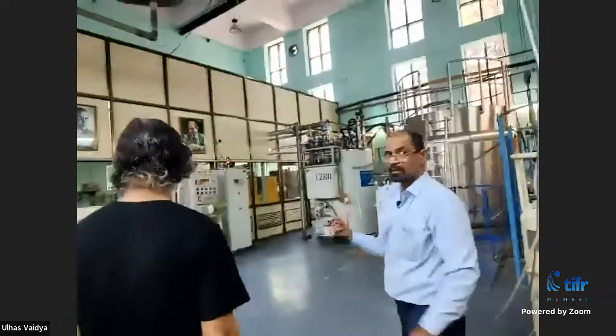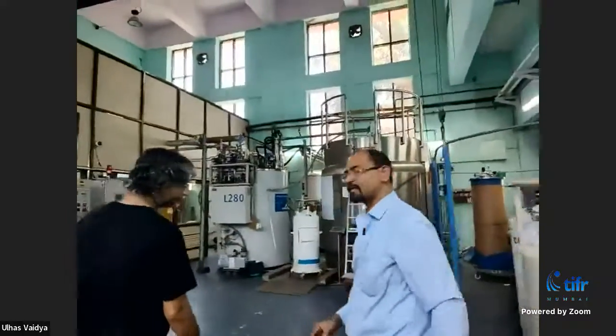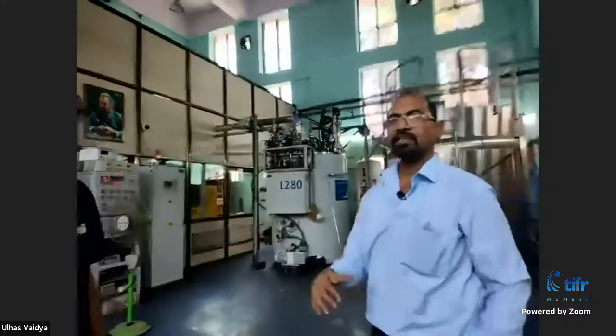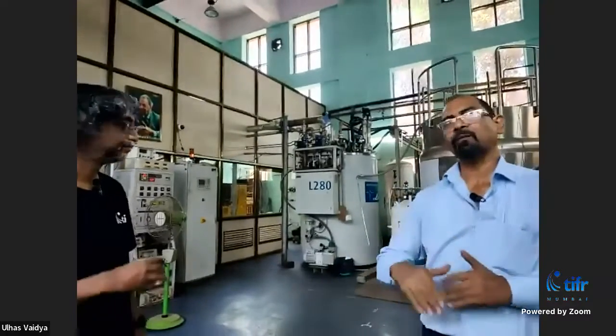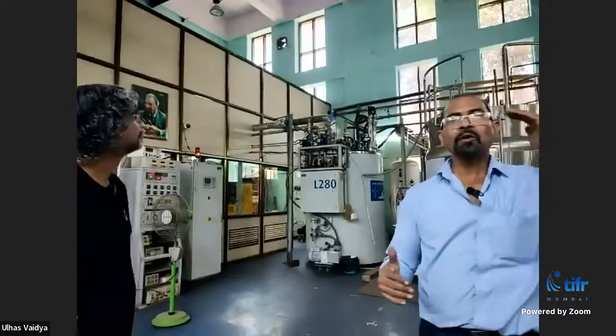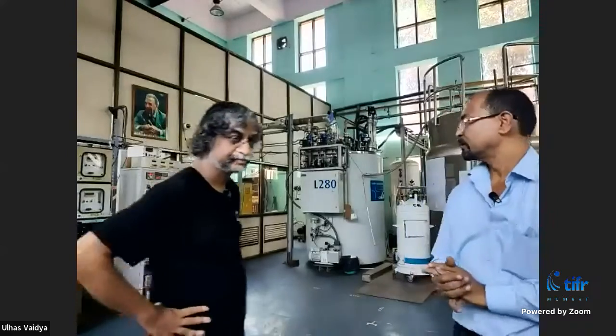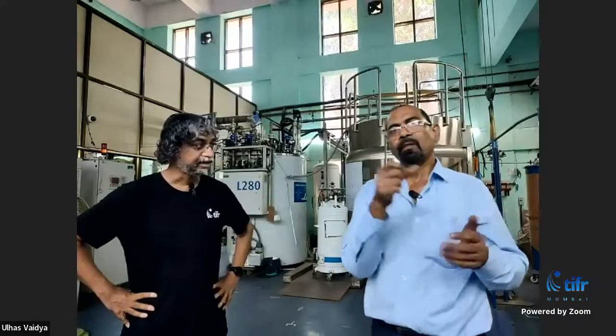Helium temperature is minus 269 degrees Celsius, or just 4.2 degrees Kelvin above absolute zero. So helium liquefaction is more challenging than liquid nitrogen, and helium is of course much more expensive. We have to buy the helium gas.